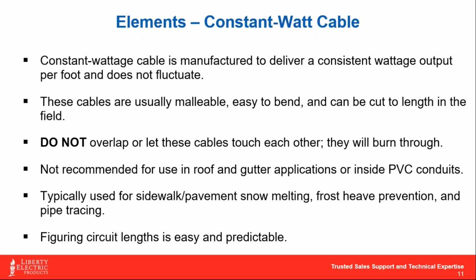All right, constant wattage cables are exactly what they say they are. They give you a constant wattage output based on whatever its rating is. And these typically will come in, let's say, 4, 5, 6, 8, 10, 12 watt a foot type cables, which is really nice as far as figuring out your maximum circuit lengths. That becomes much easier. These cables are often very flexible, easy to bend out in the field, the commercial grade stuff, and can be worked out in the field.